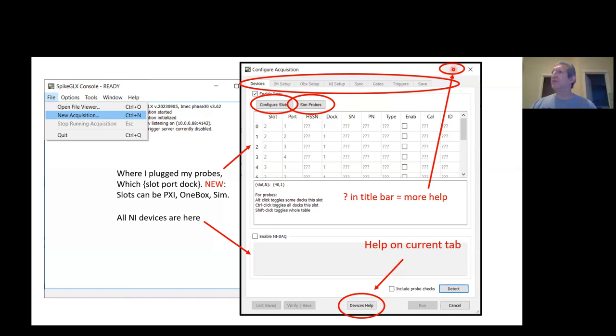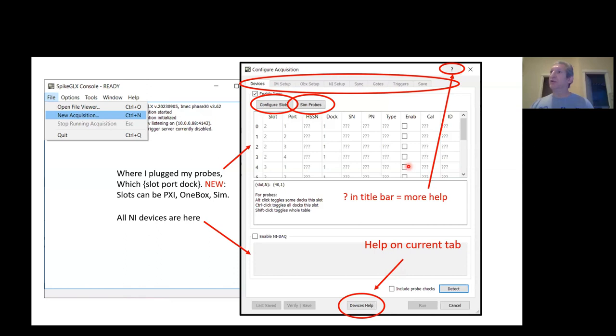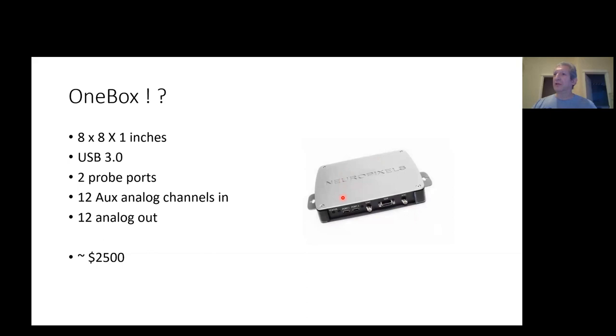I want to show you a few things about the devices tab. In this big box are all of the slots in your chassis. These are places you can plug in probes. You basically would plug probes into your chassis and then check the boxes for where you put the probes to tell SpikeGLX what you're going to do. But there's a new device coming very soon called a OneBox. It looks like this, like a pizza box. It's very small, very affordable. You can plug a few probes into it and also use it to record a few non-neural channels. This thing plugs into your computer via a USB 3.0 cable. It's not a chassis.